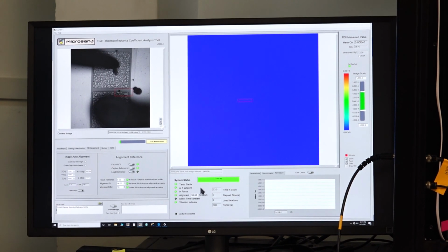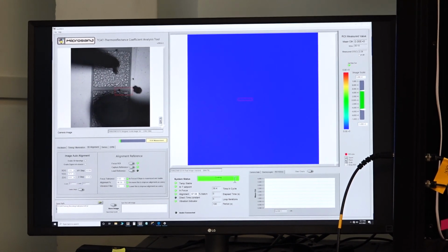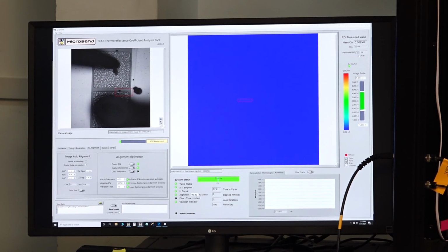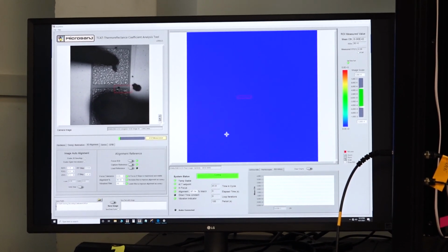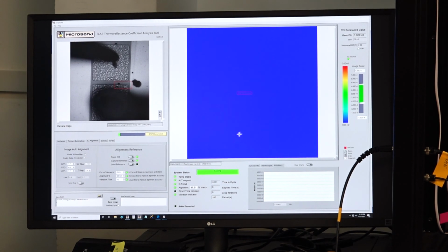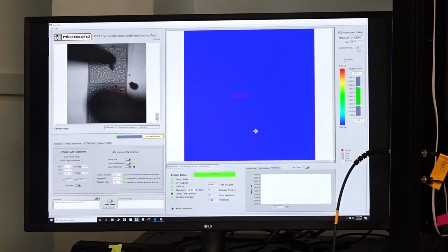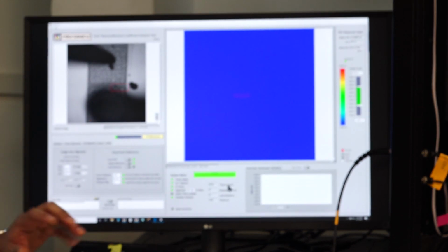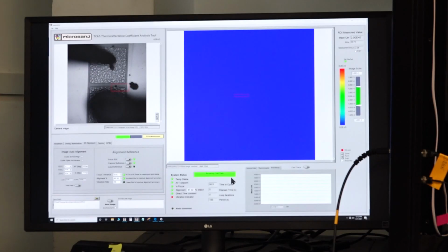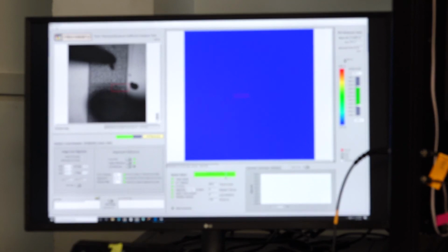Okay, so as the measurement goes on, you can see there is a status bar which shows cooling. In this phase, the device is kept to cool and it is allowed to achieve equilibrium with the room temperature. And after this cooling phase, in the ending part, the CCD will capture an image of this stabilized, cooled system. So you see acquiring cold data. It has allowed the setup to reach equilibrium with room temperature and it is acquiring cold data.